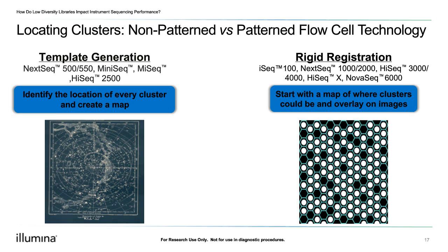For systems that use pattern flow cells, such as our HiSeq X, HiSeq 3000 and 4000, NovaSeq, iSeq, and the NextSeq 2000 systems, clusters will form in nano wells that are manufactured onto the flow cell. With a pattern flow cell, registration markers called ring fiducials are used to align a predetermined map of the ordered nano wells. On a pattern flow cell, template generation is therefore not needed. Instead, the instrument uses the first few cycles to identify wells that have clusters and which wells are empty.